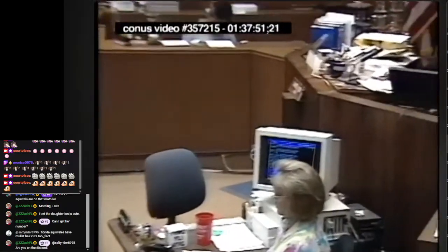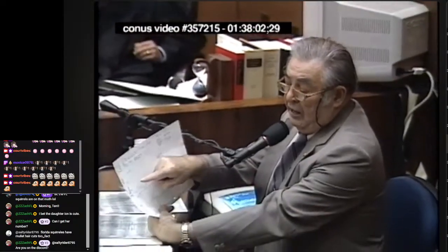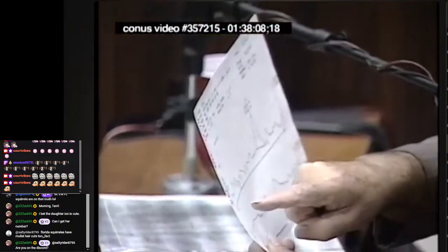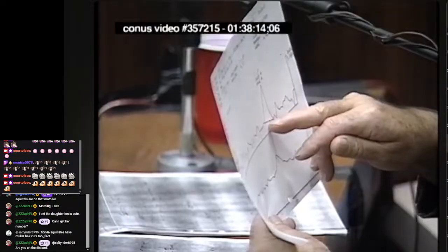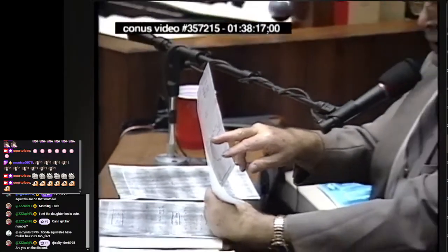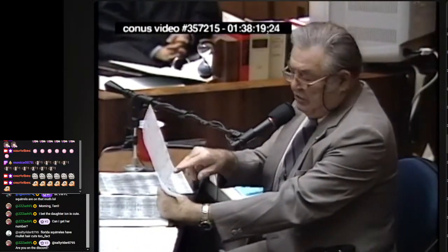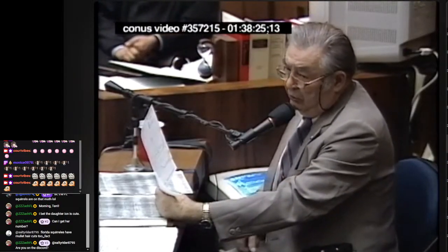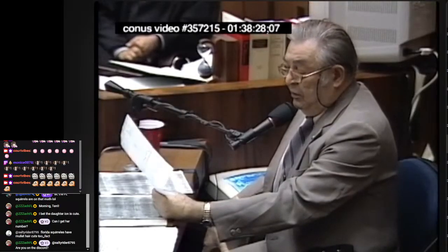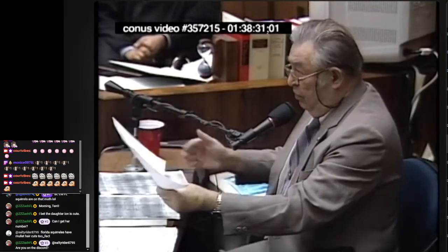It's the appearance, the presence, and the disappearance that is shown. So you can program how wide a base you want, or you can program, draw a line from a point of a certain height. You see on the left the counts are 50, 100, up to where the M over Z 160 is. There are these count numbers. And so these are height numbers, really, in a sense. So it says draw anything that has a height less than what some of the noise might be to the next point where you have that same. So you can do it in a variety of ways, but the instrument is instructed over what range to draw the line and the peak.